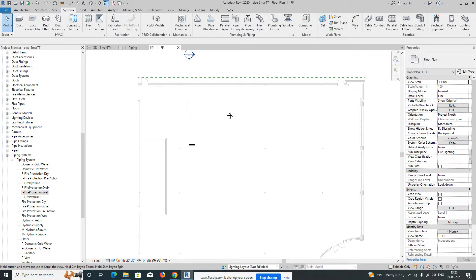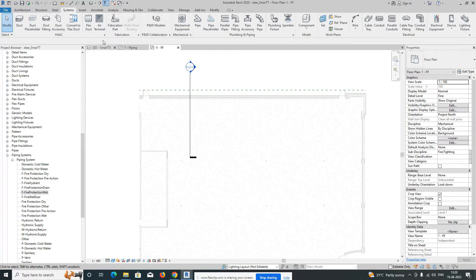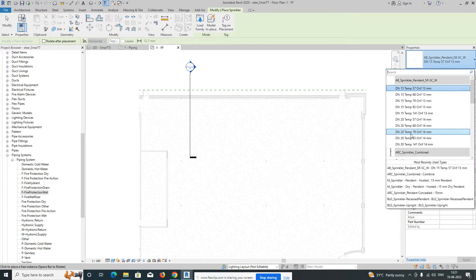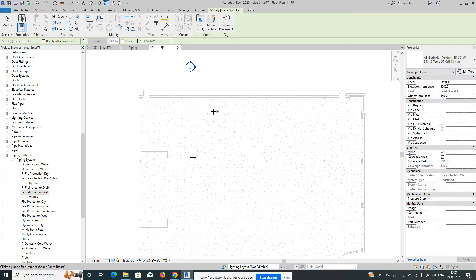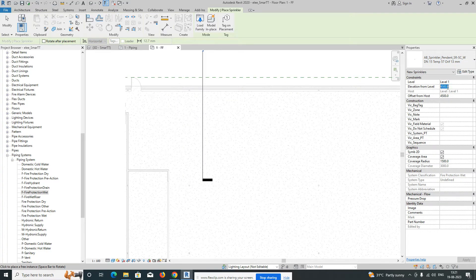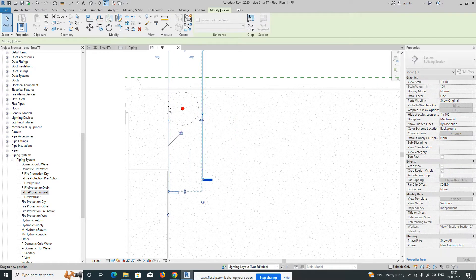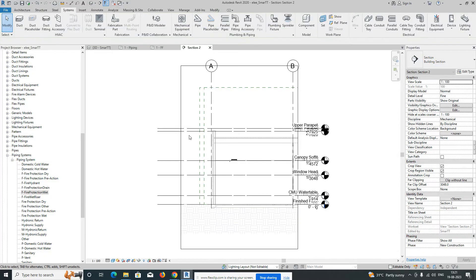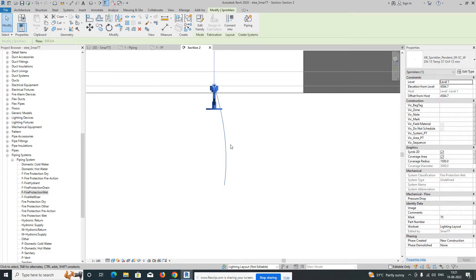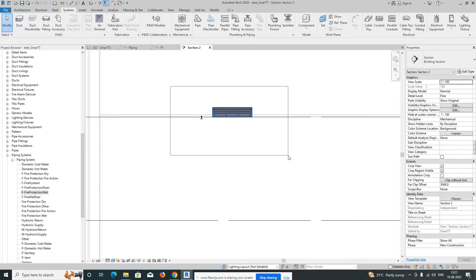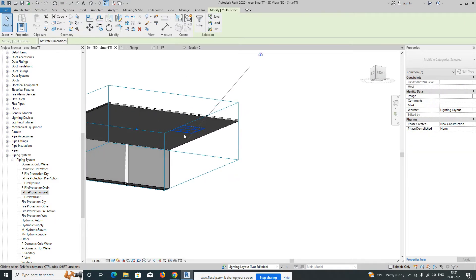Here is the sprinkler family. Go to the System tab and you will get all mechanical systems listed there — you can find the sprinkler or type 'SK' for sprinkler. The family can be downloaded from various websites. Choose whichever type you need. I'm placing this one at around 4500mm. Once placed, take a section view — the sprinkler is not fixed to the ceiling, so move it up to the ceiling.